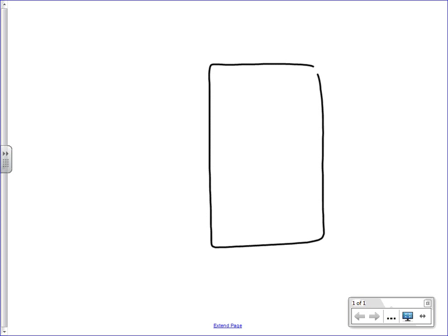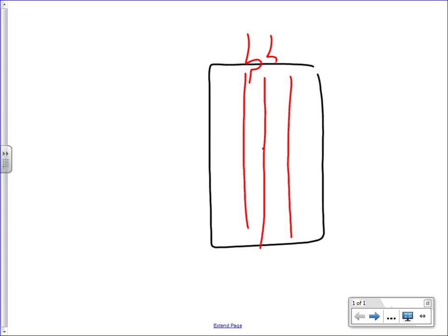So for example, I'm just going to make it very easy, simple. I have a panel and the bus is inside the panel, and I have a circuit breaker right here for this panel. Let's just pick a panel size. I have a panel size of 600 amp. This is a 600 amp panelboard, right? Now, based on my load, guys, I put a 600 amp circuit breaker. Can you guys see that the circuit breaker cannot be more than the panel is rated for? Everybody understand that?